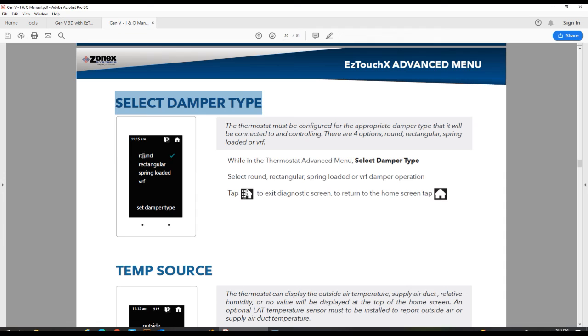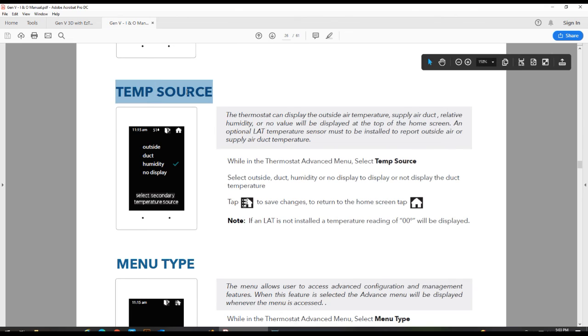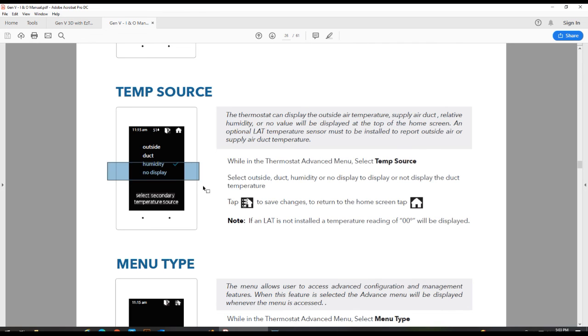Select the damper type we've gone over, your round or rectangular dampers, or if you're running a spring-loaded and/or VRF damper, make sure you set it accordingly. Each thermostat allows for a different type of temp source to be reported from the thermostat. In this case, all thermostats come with a humidity sensor. It reads the relative humidity. So if you want to display the humidity at the top of the thermostat, you can go ahead and display it. Do note we do not control dehumidification, so this is merely a reading to let you know what the humidity is in the room. If you want to have it not show up at all, you can go ahead and select the no display. Do note that the outside and the duct displays are not available on the Gen V controller, and there's no need to bother with those.